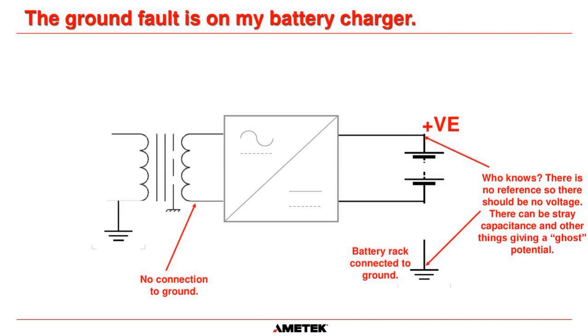So as you can see here, I've now drawn the transformer and we have no connection to ground here. Okay. And I've put in a charger. Okay. And then the charger has its positive terminal and its negative terminal. And if we took a multimeter and we went between positive and ground, guess what? You shouldn't measure any voltage. But once again, there are things that could make you measure a voltage, and I'll go into those in just a moment. But it can be stray capacitance, other parts of the circuit. I'll explain in a moment. But in theory, if you go from positive to ground and negative to ground, you should measure 0 because there is no potential, because there is no reference. Okay.